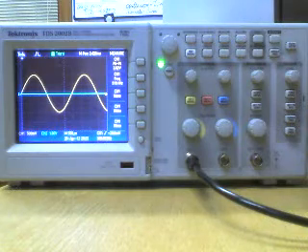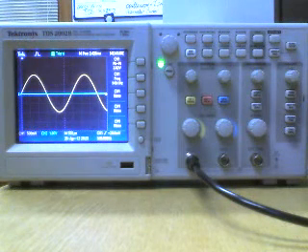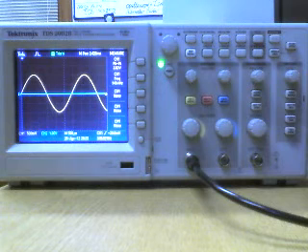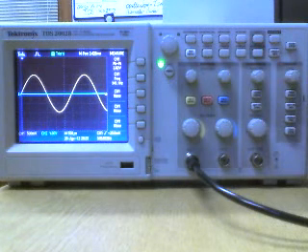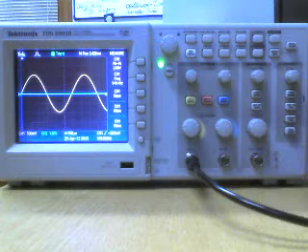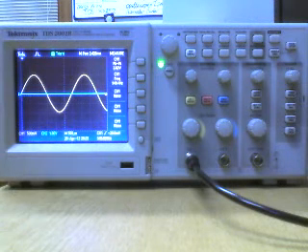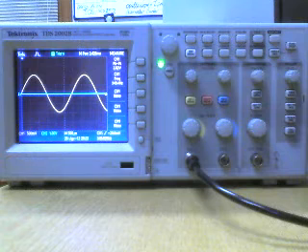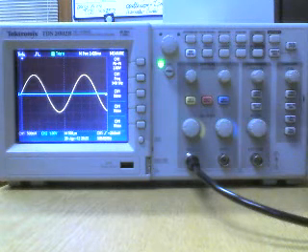That takes care of the auto measure function, but unfortunately auto measure doesn't work as well as you would think it does. Now, on a Tektronix oscilloscope, it only has a small amount of what's called memory depth.